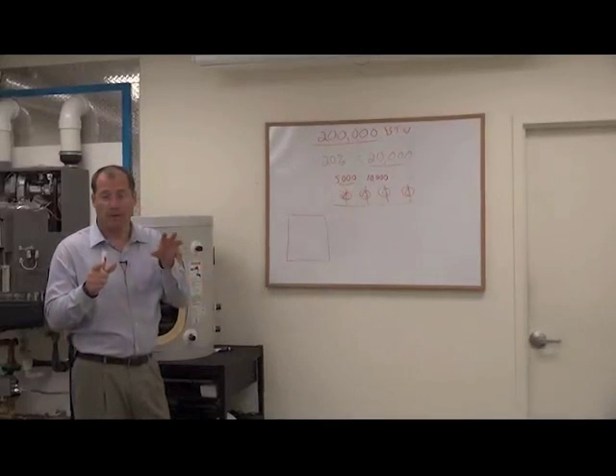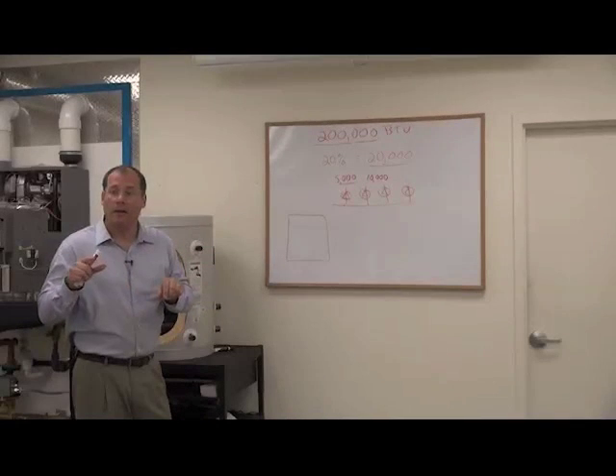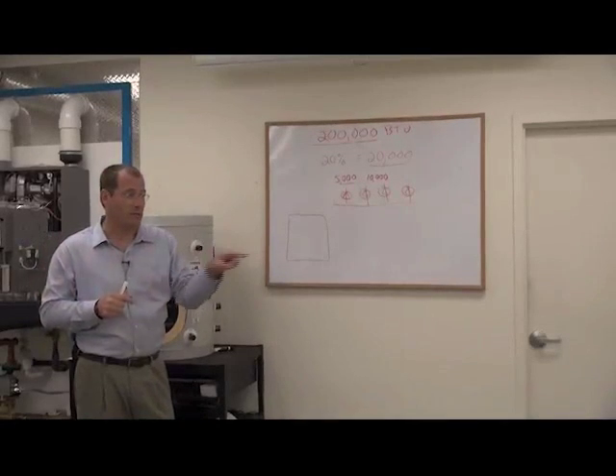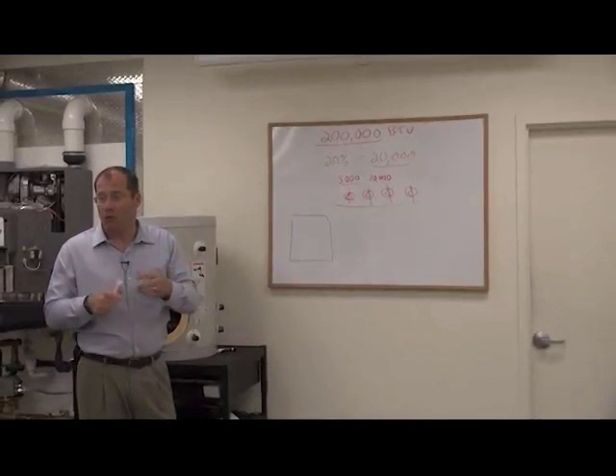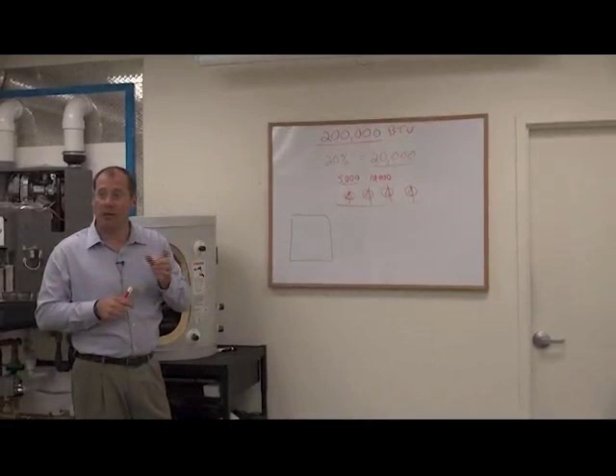The best way is to perform a heat loss and gain calculation, which looks at the envelope of the house and says, if I want to be 70 inside and it's zero outside, how many BTUs do I need in this room and in this room and in this room? Add all those up and that's your total BTU requirement. That's the right way to size it.